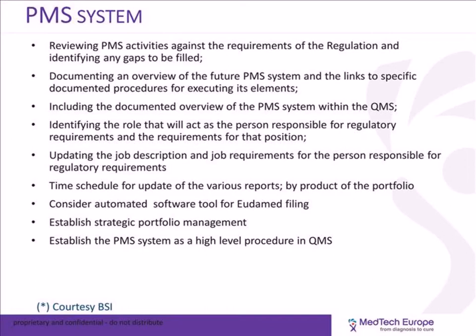The time schedule for update of the reports needs to be defined, and you can refer to the takeaway slide we reviewed before. This is very dependent on the portfolio of your product. If you have class 1, class 2, or class 3, or implants, this will drive a very different pattern of report production and resources required.